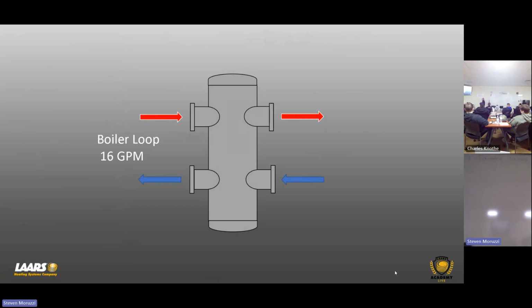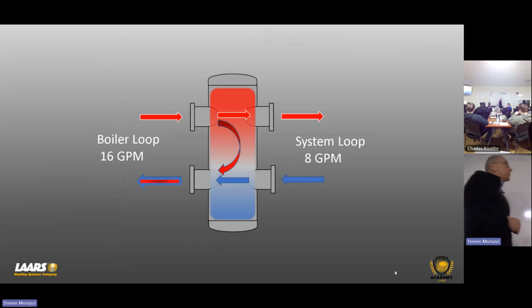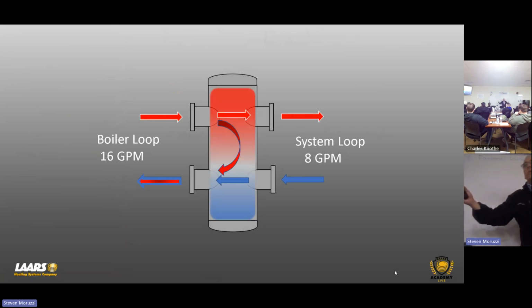All right, in this example, my boiler pump is fixed at 16 gallons a minute. System pump is, now I've only got 2 zones, 2 3/4-inch zones, for example, of 4 GPM each. What happens here? So I'm pushing 16 GPM into that low loss header, and I'm pulling 16 out. And if I draw a dotted line right down the center, I'm decoupling my system loop from my boiler loop. Both are getting proper flow rate. And that's what a low loss header is. Works just like primary, secondary, okay? And there's many different low loss headers. Rath sells the Caleffi low loss header. Here's a small one, okay? How many GPM, how many gallons do you guys go up to on the large sizes?